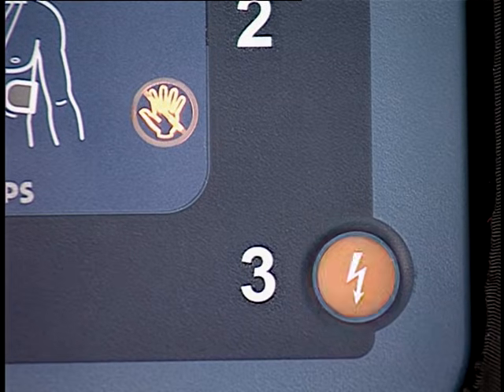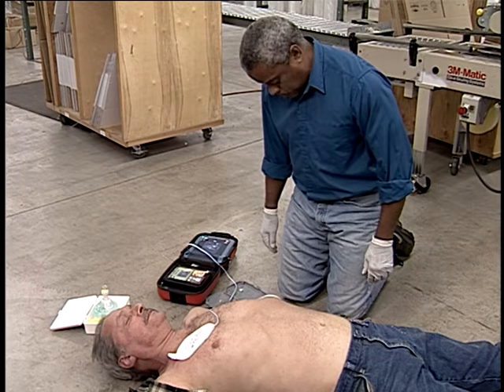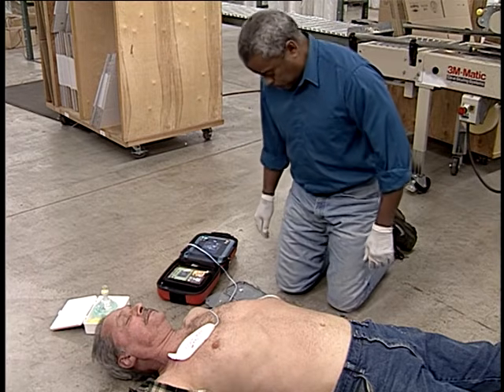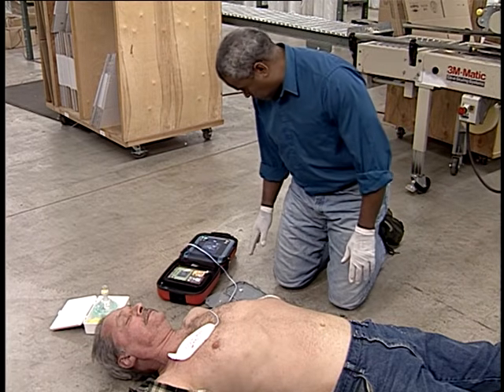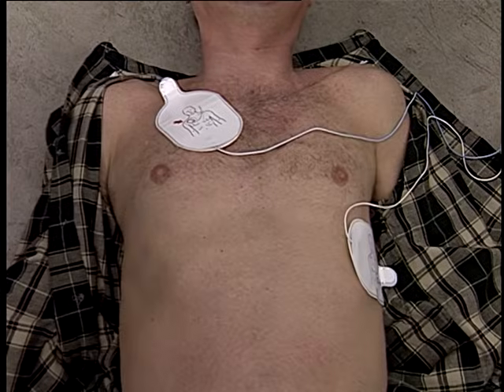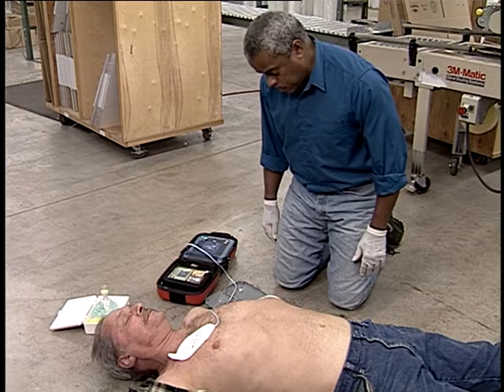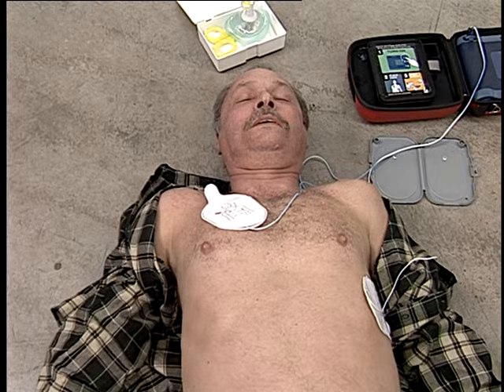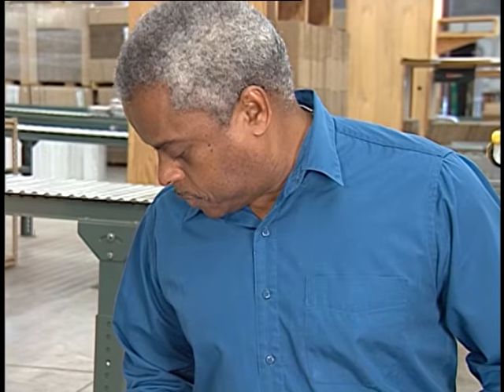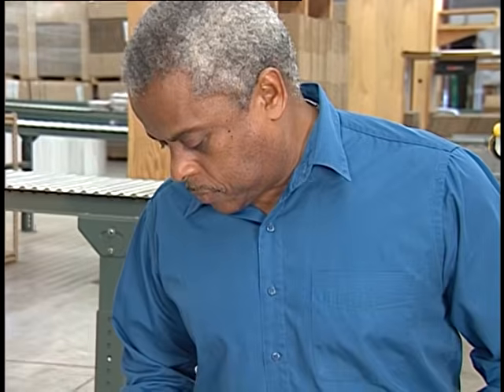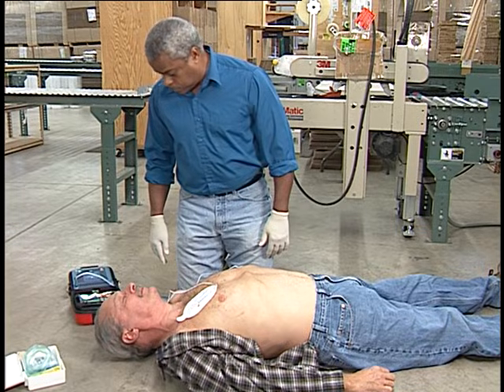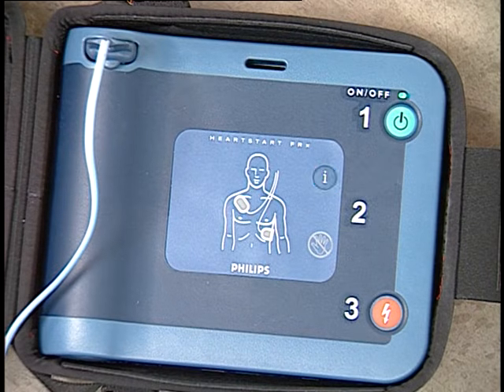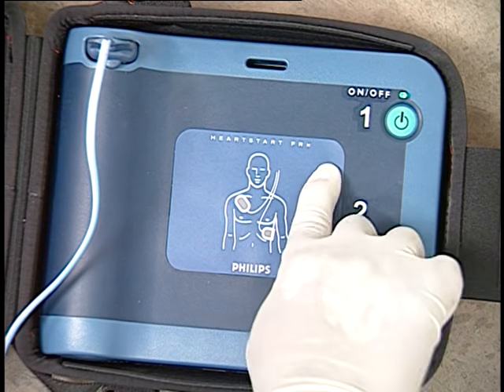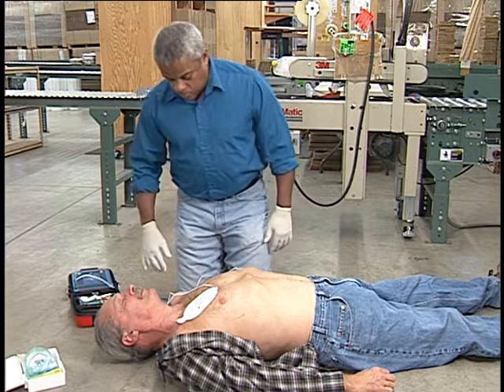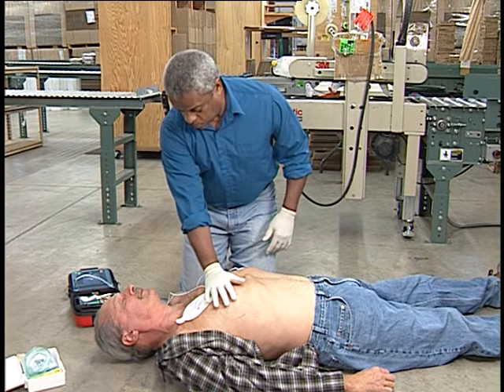Before pressing the button to deliver the shock, you must make certain that no one is touching the patient. Press the orange shock button to deliver the shock. For safety reasons, the shock will not be delivered until you press the button. After delivering the shock, the FRx immediately tells you to begin CPR and provides a CPR interval. During the first 30 seconds of the interval, you can press the flashing blue I button and the FRx will provide CPR coaching. Place the heel of one hand in the center of the chest, between the nipples.